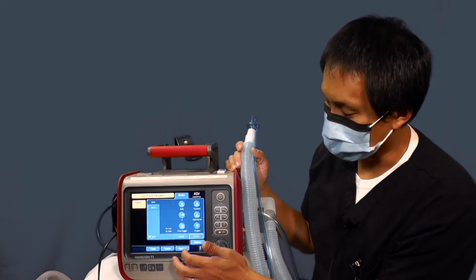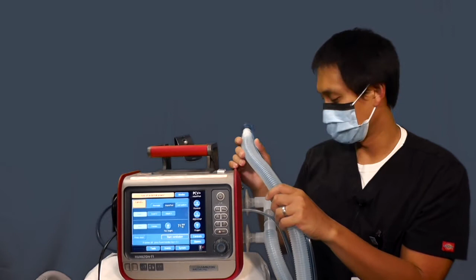and not your true total pressure. The other thing you'll notice is that it has a flow trigger. On the Impact, it's a pressure trigger of minus to plus scale. On this, it's a flow trigger scale. So typically we leave it on a default of 5, which is what is defaulted on this machine from the factory, unless you want to change it otherwise.